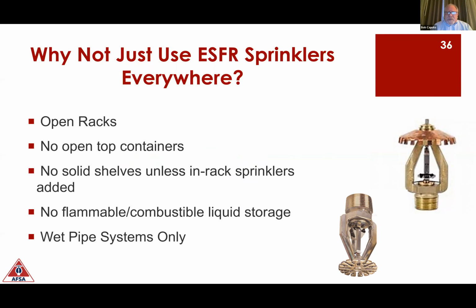So a lot of times people who know about ESFR sprinklers ask me, why don't we just put in ESFR sprinklers? They're the best. We don't have to put in rack sprinklers. And why don't we just do that? Well, the answer to that is you can only use ESFR sprinklers in open racks with no open top containers. You can't have solid shelves unless you add in-rack sprinklers, and they won't protect flammable or combustible liquid storage. Plus, you can only use ESFR sprinklers in a wet pipe system. Most of you probably know that gas will float on water.